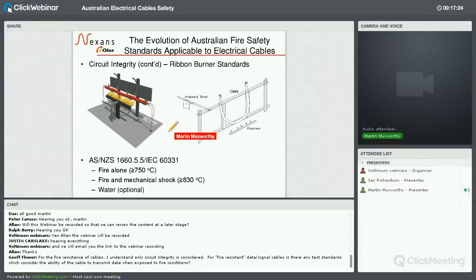You can have fire alone, which is as depicted on the image at the left. It consists of the ribbon burner, as you can see there, and then the cable sample is supported, clamped near its ends, and then there are two rings that are within the fire or the flame region, and the whole idea is to obviously ensure that the cable continues to operate, so there's no short circuit between conductors, and there's also no short circuit between the conductor and these metal rings. So you can have things like fire alone, and typically the fire alone test is done at 750 degrees, or you can have fire and mechanical shock.